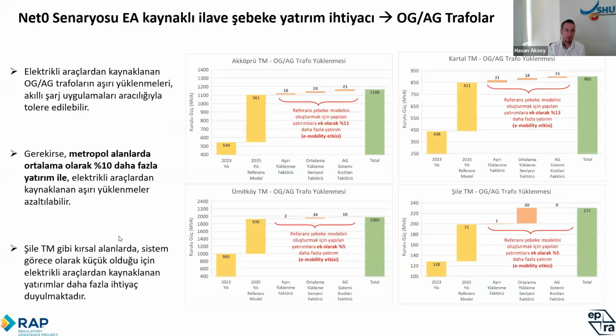When we look at the results, with electric vehicles in the reference grid model, the overload caused by EVs on LV-MV transformers can be reduced with an average of 10% more investment in metropolitan areas compared to the reference grid model without EVs. For instance, in rural areas such as certain transformer centers, investment from electric vehicles is needed because the system is relatively small, so the investment needs to be higher in such areas.